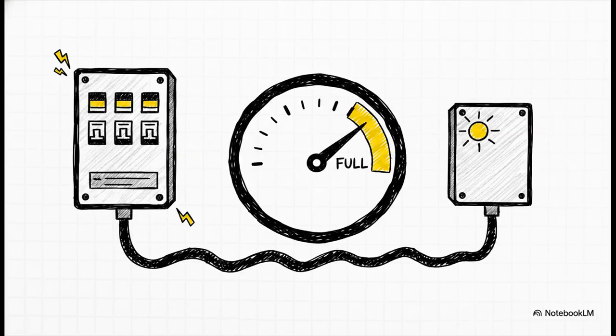Here is a critical pre-construction hurdle that catches a lot of folks off guard: the 120% rule, outlined in NEC 690.64. Basically, it dictates that the combined current from your main utility service panel and your solar inverter cannot exceed 120% of your electrical panel's busbar rating. If you ignore this, you risk dangerous overheating and potential electrical fires. Factoring this mathematical rule in early ensures your infrastructure can safely handle added solar capacity, saving you from having to rip out and replace entire electrical panels at the very end of construction.